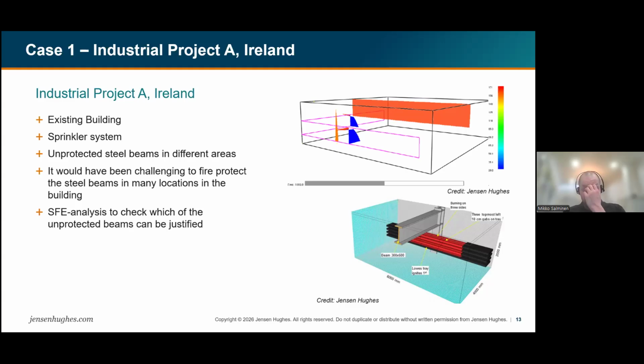Which is really a reliable system usually, and especially in this case, they really had a more reliable system than usually. And per prescriptive design, they would have needed to protect many steel beams there, but for some reason they hadn't protected those, and we investigated if we could justify it in some areas. So because it would have been really challenging to protect them at that stage of the project, we investigated how much we can rely on the sprinkler system, and if the sprinkler system doesn't operate, what would happen then.